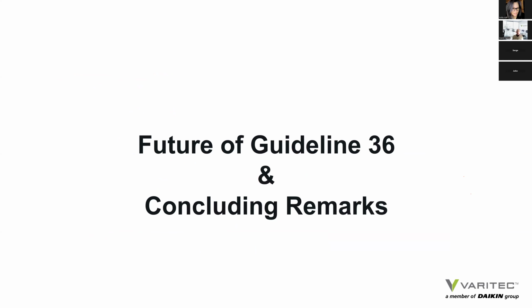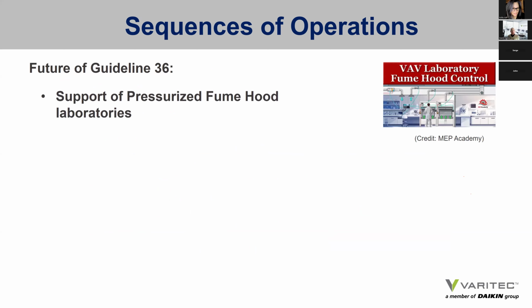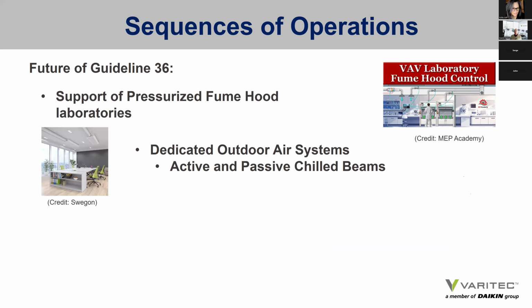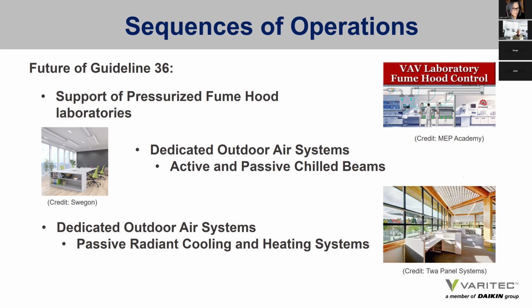So the future of Guideline 36, in concluding remarks. The future of Guideline 36, where is it going? The guideline is moving into supporting pressurized fume hood laboratories. It is moving to provide language or sequences for dedicated outdoor air systems, 100% outside air systems that serve active or passive chilled beams. Provide dedicated outdoor air systems that use passive radiant cooling and heating systems, perhaps arguably one of the most efficient design solutions in the market we have today.